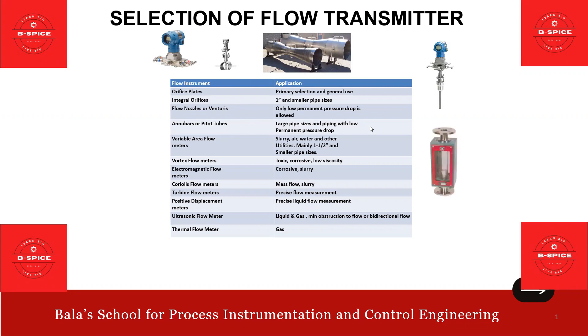Variable area flow meters: rotameter is used for slurry, air, water, and other utilities — mainly for 1.5 inch and smaller pipe size. Vortex flow meter is used for toxic, corrosive, and low viscosity applications.